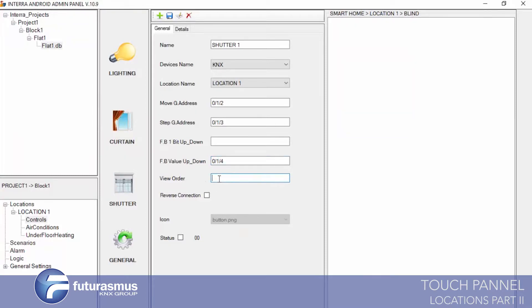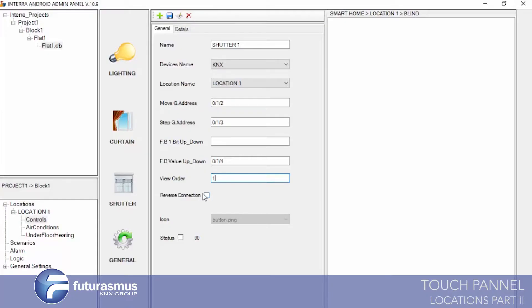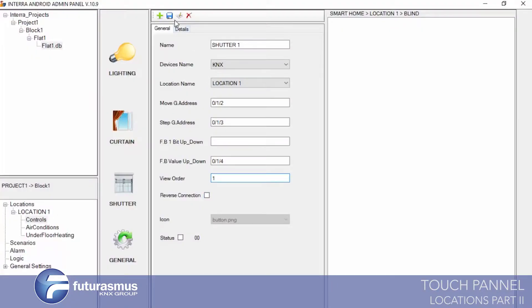Also, we have a view order for screen ordering — you can define this. If you don't define it, objects will show in the touch panel screen by adding date, so the first added will show first. Also, we have reverse connection again — you can reverse up or down commands with this control. We will save this shutter object with reverse connection, and while doing tests we can see how it works.